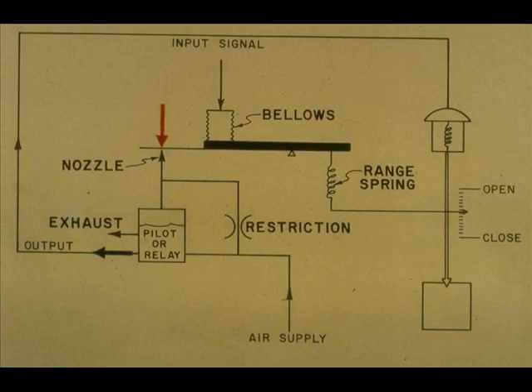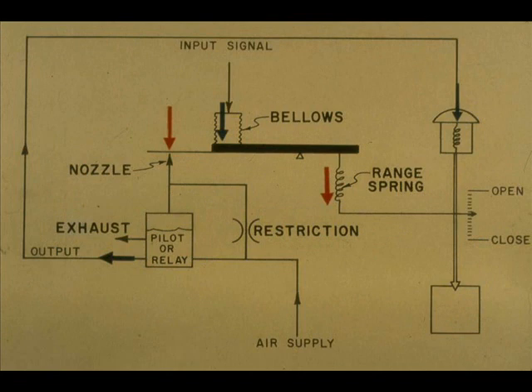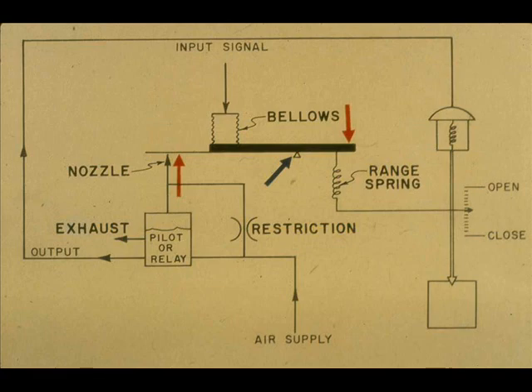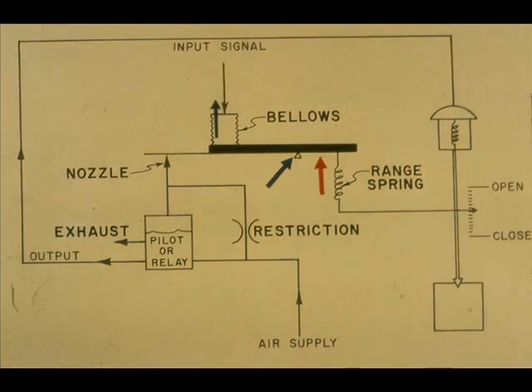When the input signal increases, the flapper covers the nozzle. The relay output increases, making the valve stem lower, which produces an increased downward pull on the beam. The beam pivots at the fulcrum and uncovers the nozzle, and the system is again in equilibrium. It will remain there until a disturbance occurs, such as an input change or a valve stem load change. On a decreasing input signal, the actions are the reverse of those resulting from an increased signal.